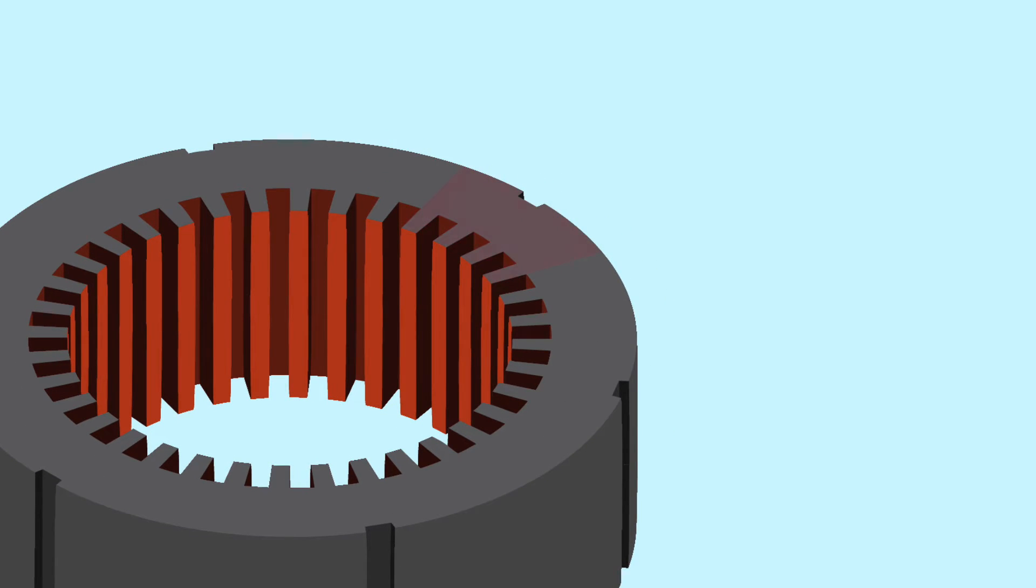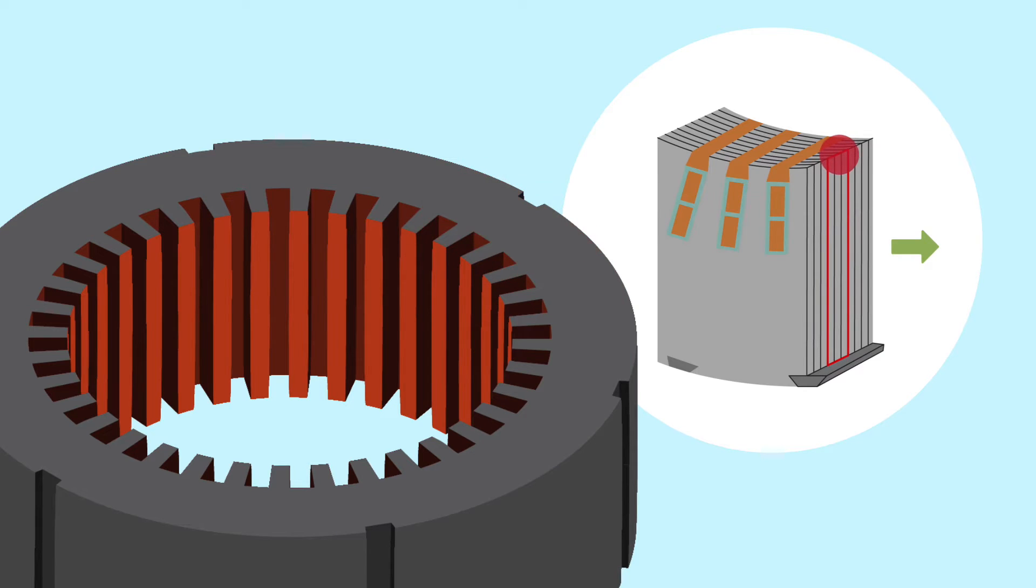A short between two or more layers lead to higher local eddy currents. This again can lead to local hotspots, which in a worst case scenario can even cause a complete damage of the machine.